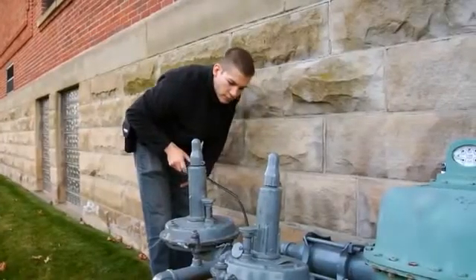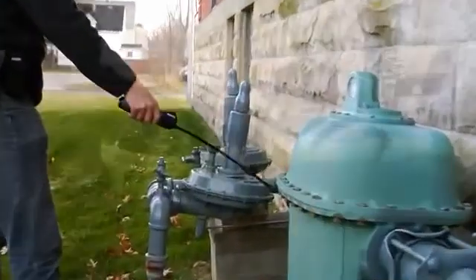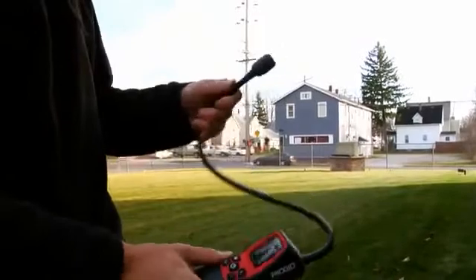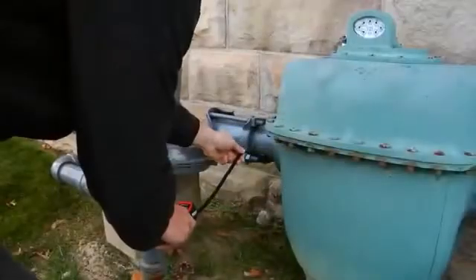High and low sensitivity levels allow for detection in even the lowest concentrations. The sensor can detect from zero to 6,400 parts per million. A 16-inch flexible probe allows for detection in hard-to-reach areas, while the sensor has an expected life of five years.